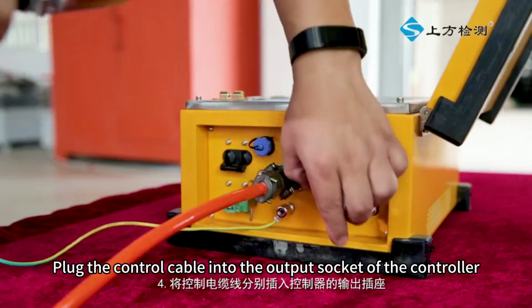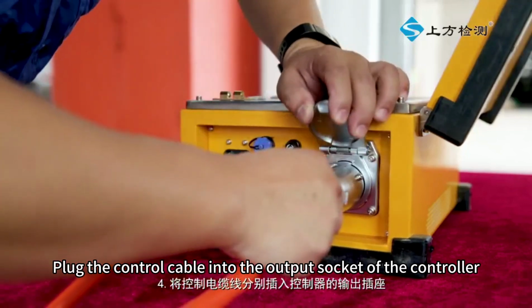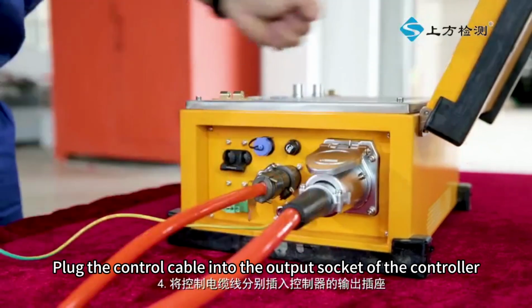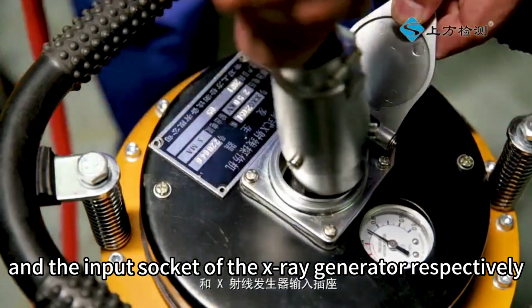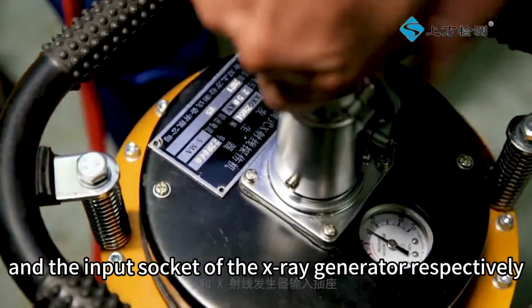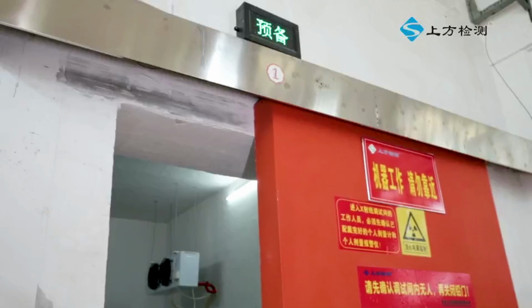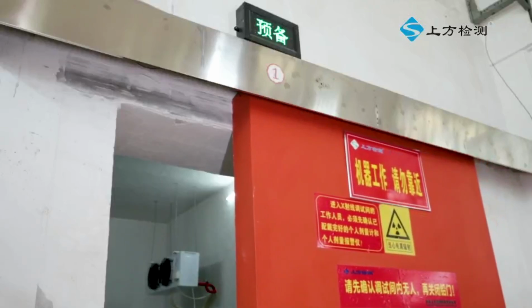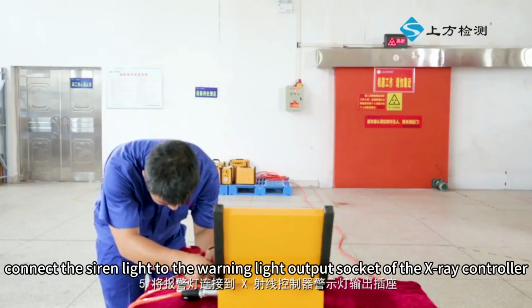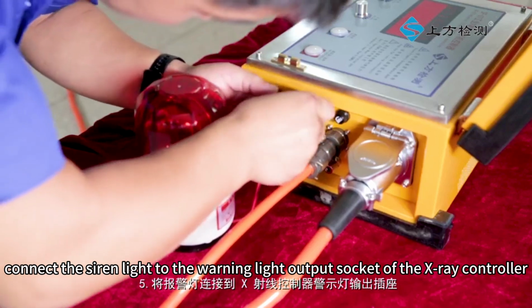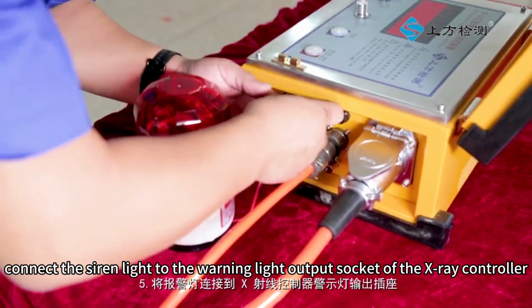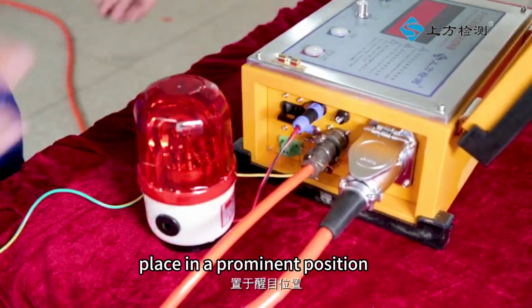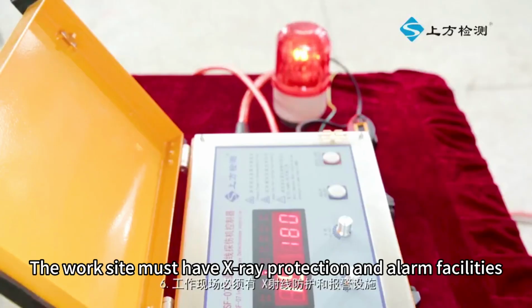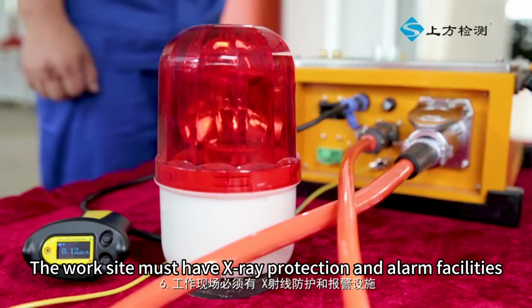Plug the control cable into the output socket of the controller and the input socket of the X-ray generator respectively. Connect the siren light to the warning light output socket of the X-ray controller, and place it in a prominent position. The work site must have X-ray protection and alarm facilities.